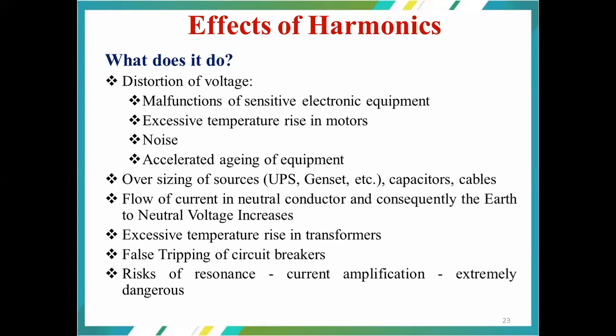Due to continuous exposure to the harmonic components, accelerated aging of the equipment will occur. That means due to this excessive temperature rise or the vibrations, all the equipment connected to the grid system is going to have accelerated aging. The next one is the oversizing of the sources. Due to the presence of these harmonic components, the reactive power requirement is going to be larger. Thereby, oversizing of sources like UPS, generators, etc. may result, and you are supposed to go for a larger rating.